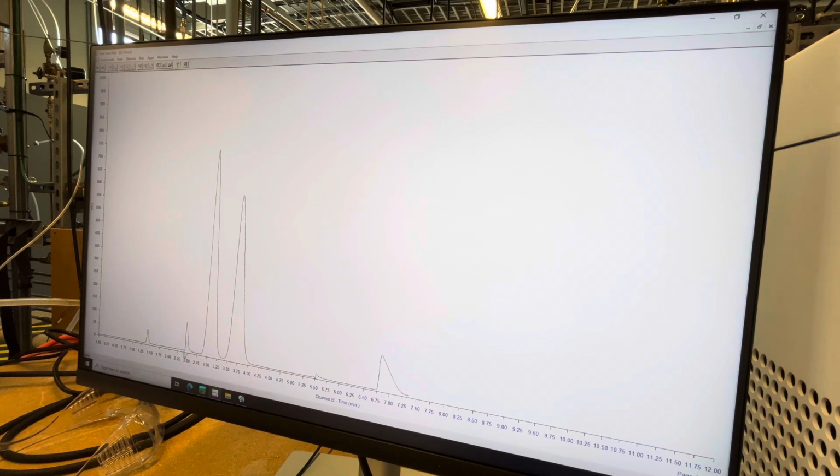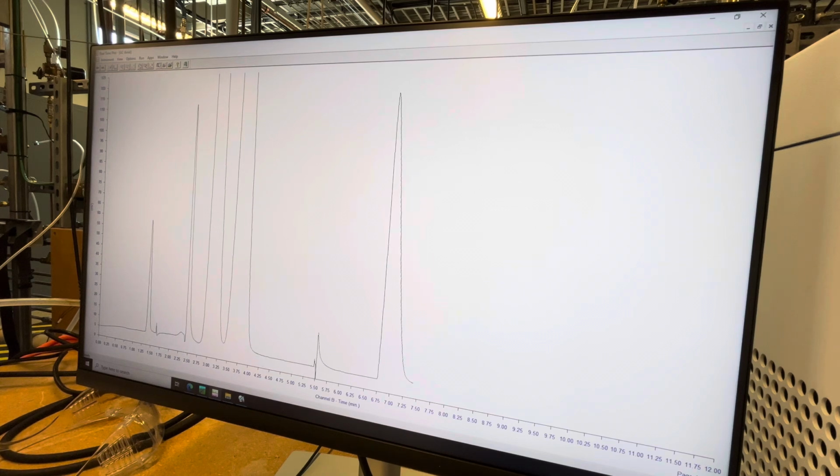That's carbon dioxide. Yeah, so it's 1% now. We've adjusted this valve timing because when we run a lot of carbon dioxide, at like 60%, it elutes over here. It starts to come out big here and then tails down. So I've set this timing a little bit earlier than if you're running a low amount, which is a little more right shifted, so that what's happening right now is we're clipping a small portion of that tail, and this CO2 is going to the methanizer.